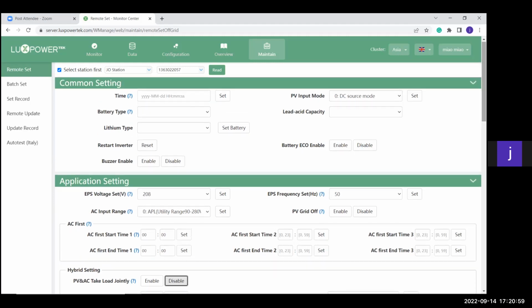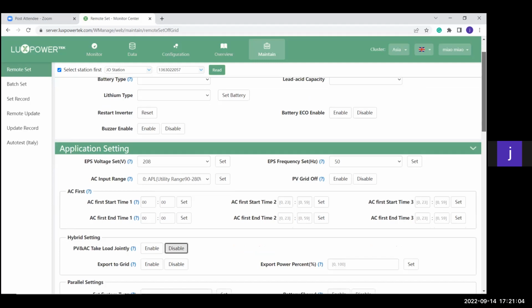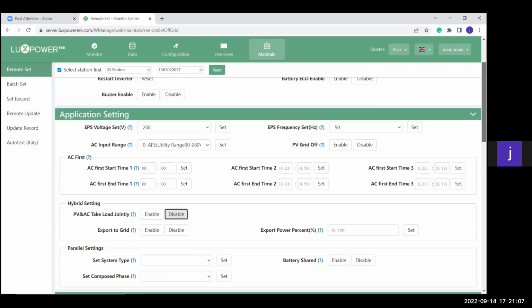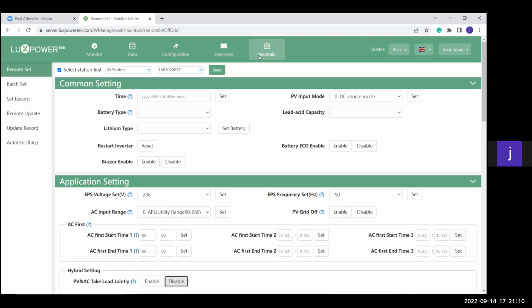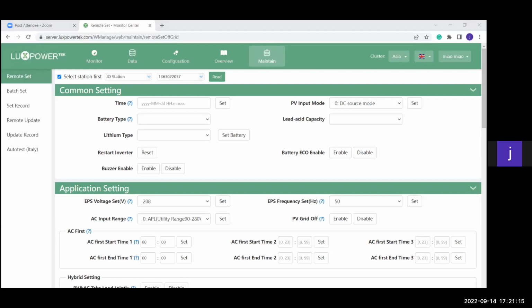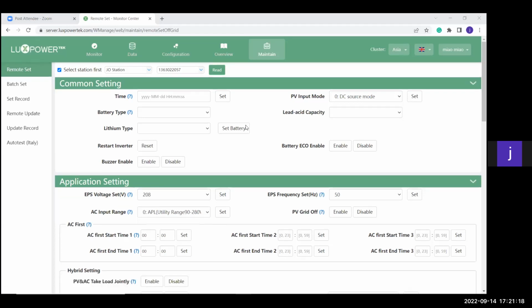So if you'd like a 12 kilowatt single phase unit or a 10 kilowatt single phase unit, Luxpower brings them out as well. I'll put the data sheets in the chat so that you can have a look. Something interesting about the data sheets on the Luxpower inverters: my 10 kilowatt unit can handle up to 14 kilowatts for 10 minutes, 16 kilowatts for 5 minutes, and 20 kilowatts for half a second before it goes into overload mode. I'm just quickly going to get everything shared here.